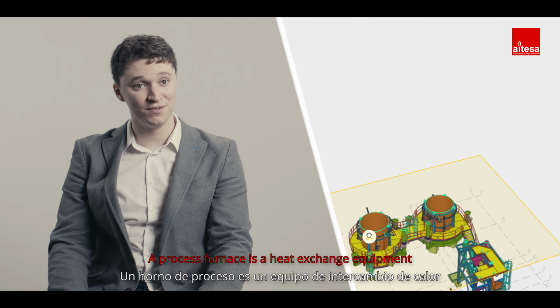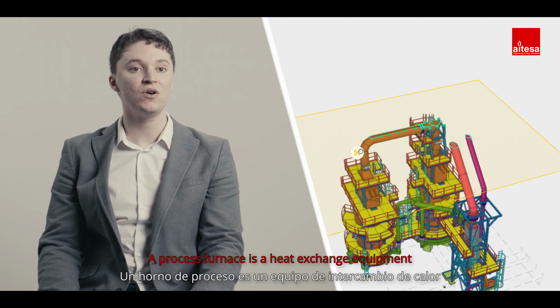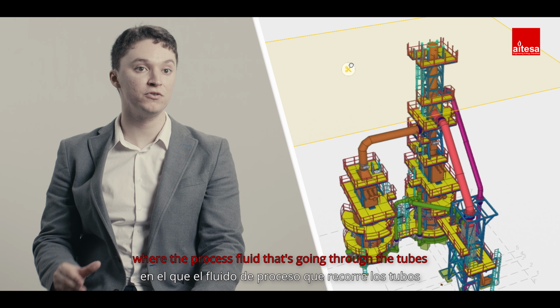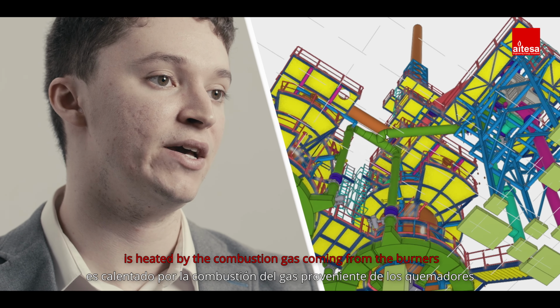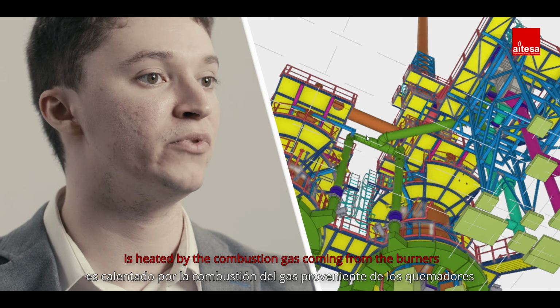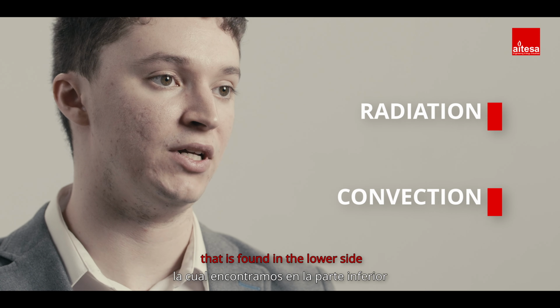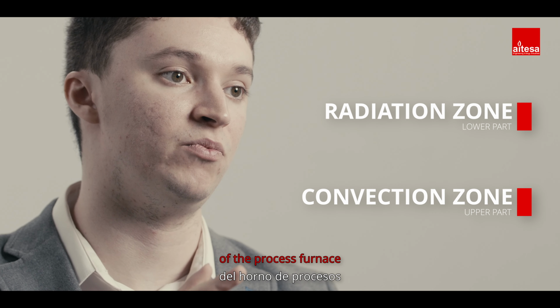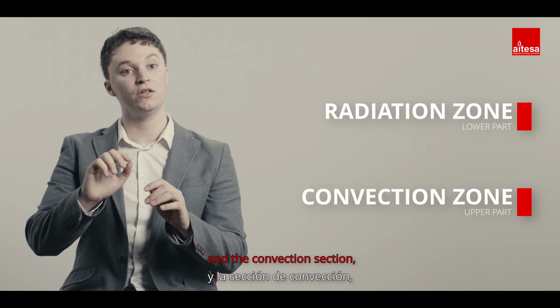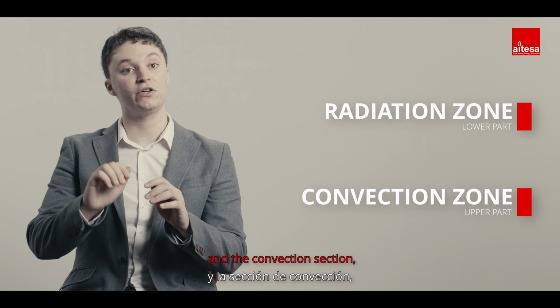A process furnace is a heat exchange equipment where the process fluid that's going through the tubes is heated by the combustion gas coming from the burners on the lower side of the process furnace. There are two very important parts that we need to differentiate in a process furnace. That would be the radiation section that is found in the lower side of the process furnace and the convection section, which is in the upper side.